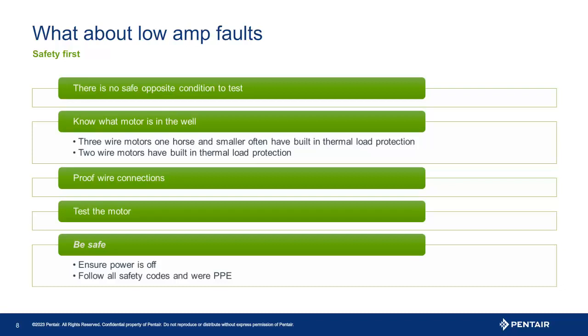What if the drive starts with a low amp fault? Well, first, there is no way to create the opposite fault, a high amp fault, safely. So do not attempt to. So, what to do?